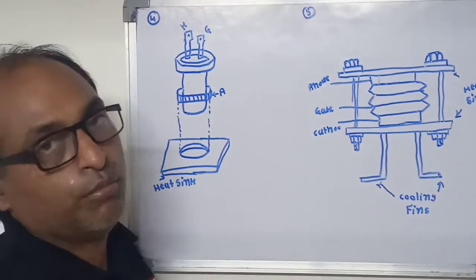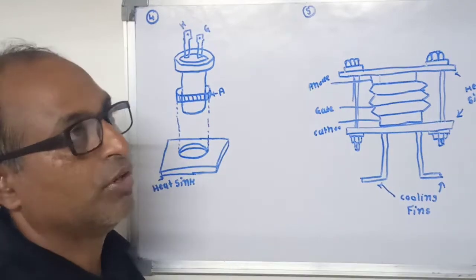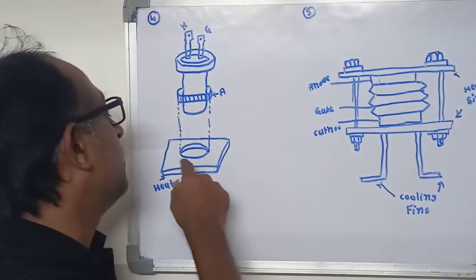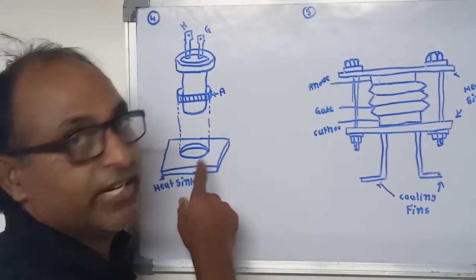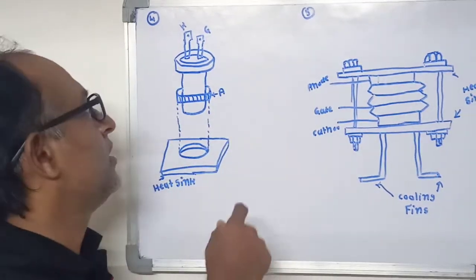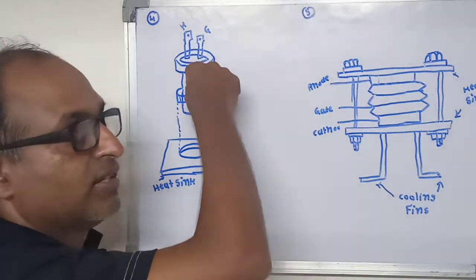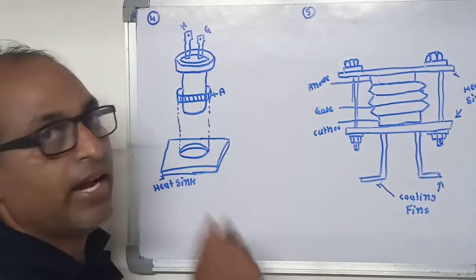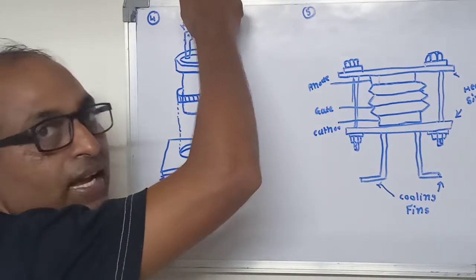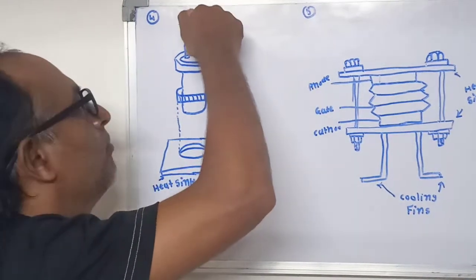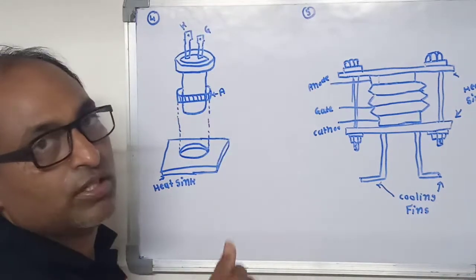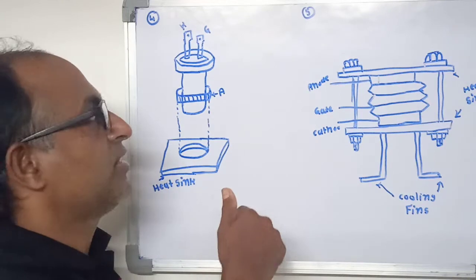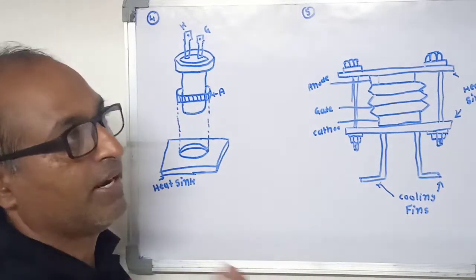Press fit mounting. It is designed for installation of SCR into undersized holes provided on the heat sink. The installation of these SCRs may be done by using a vise and pressure onto the SCRs using wooden blocks. For higher capacity SCRs, the installation may be done using a hydraulic ram.